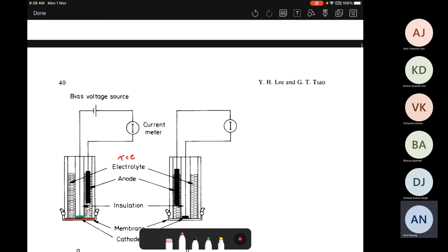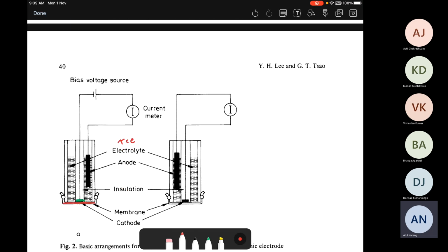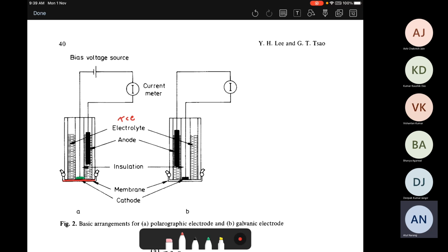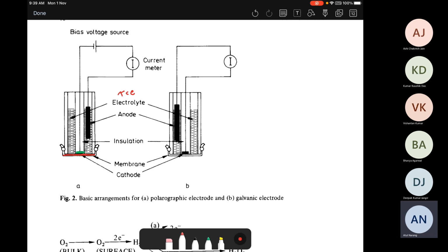So the electrons essentially flow from the so-called anode, where they're being deposited, into the cathode. The chloride comes and dumps the electron, and at the cathode, the oxygen receives the electron. And over a period of time, you will find that the KCl gets depleted because these chloride ions are being used up. So periodically, you have to come and replenish the electrolyte. So this is the basic principle on which it works.